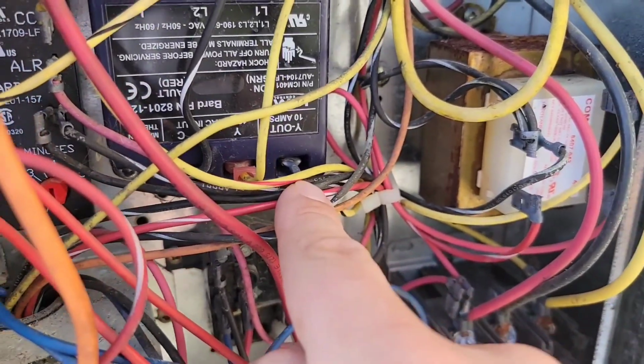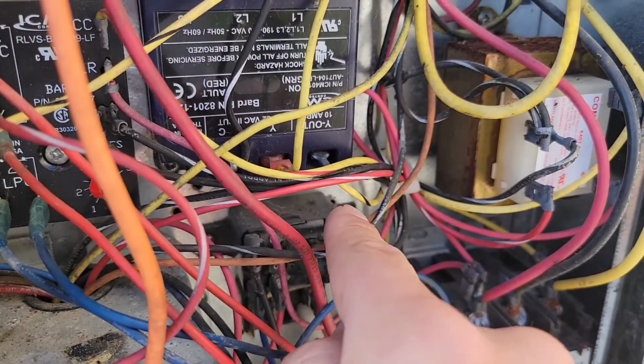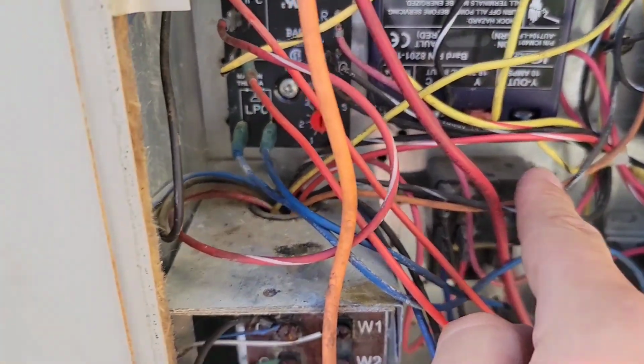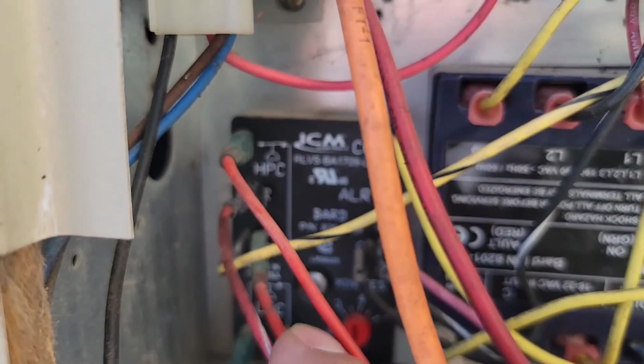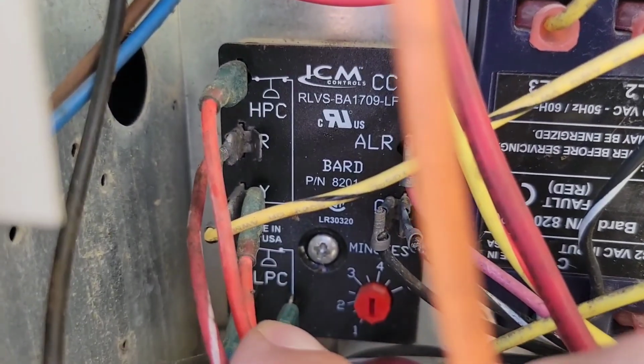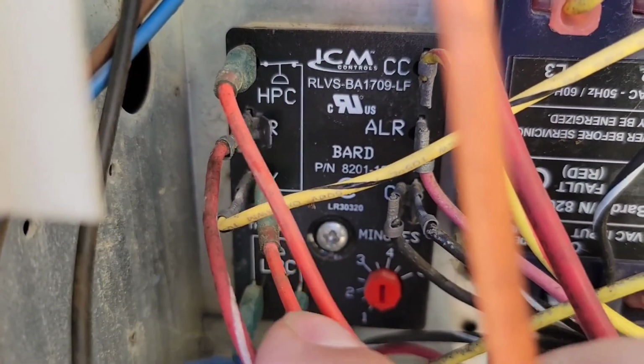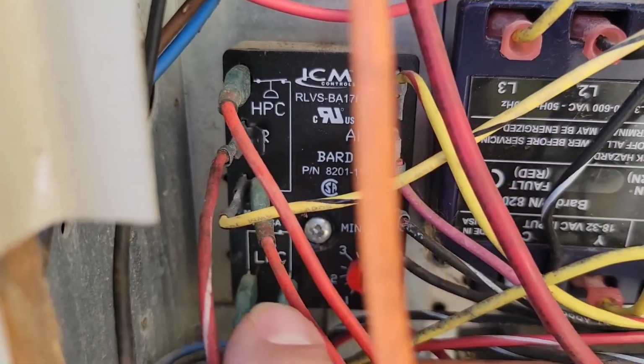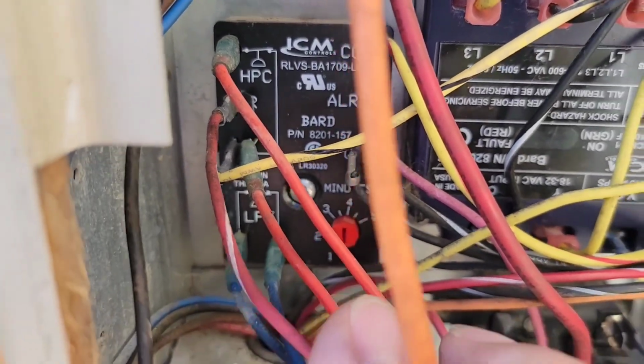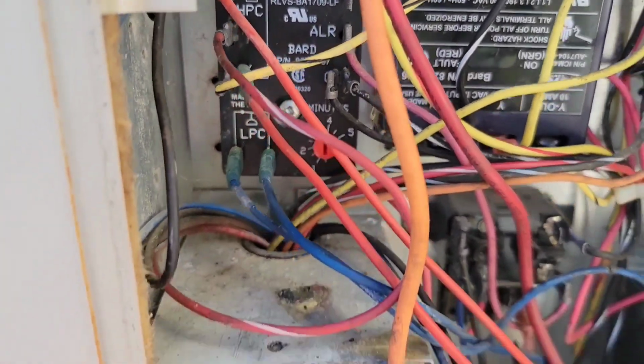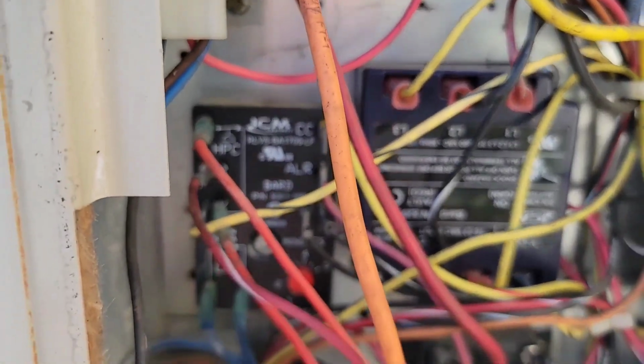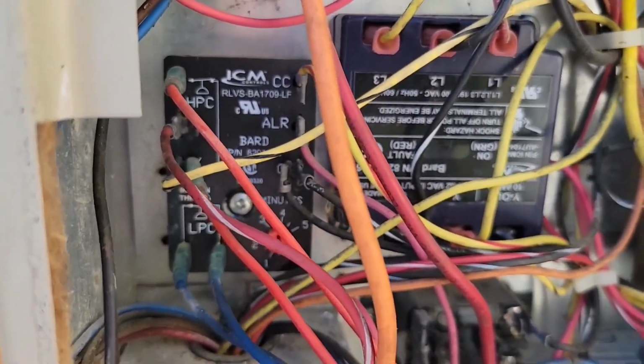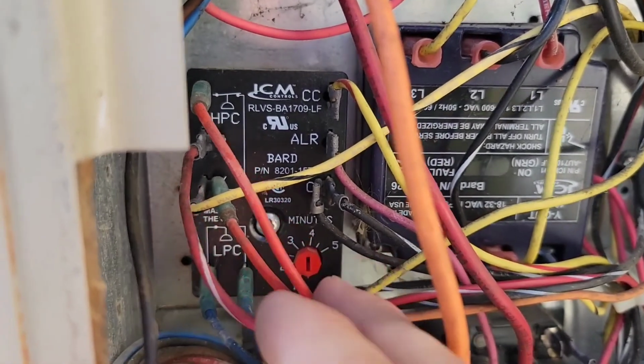So we go to the Y out. Where does this wire go? It's yellow and looks like black. It goes right here. Okay, it goes into, and it says Y right there. It goes into this time delay relay control. So next we would check from the C to the Y going into this control. And then I'll go ahead and show you where it goes next.